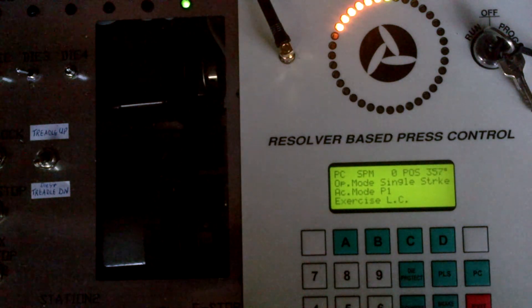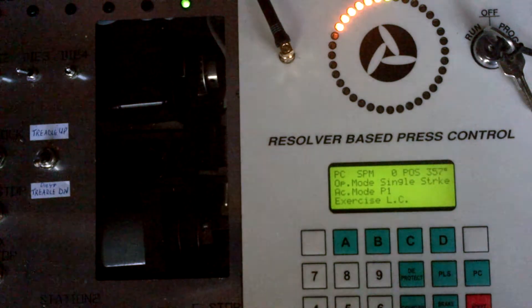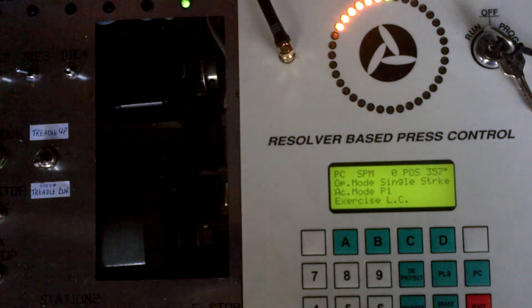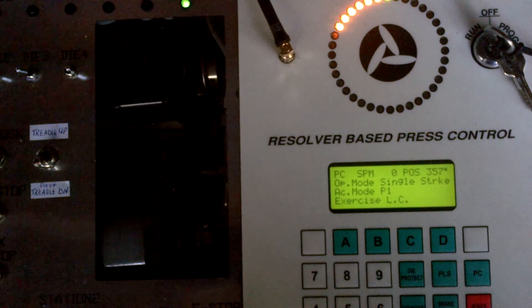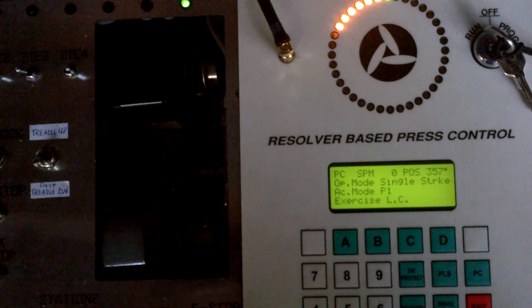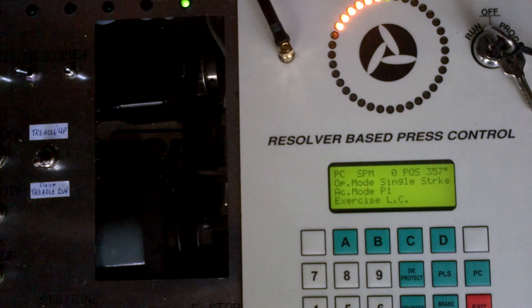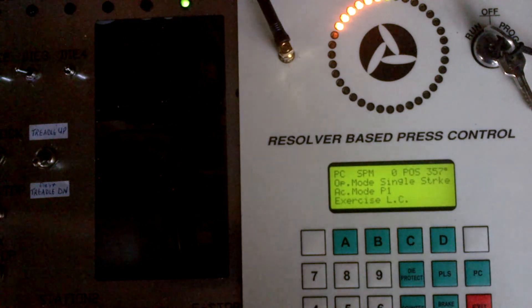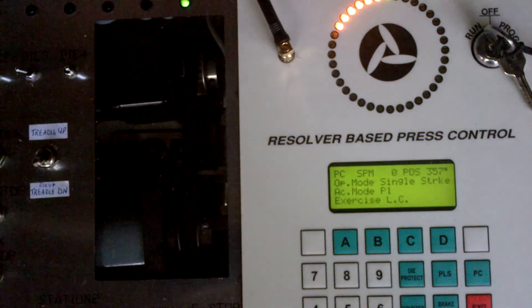So it's a very simple process. It might take several strokes to get it by single stroking and following the prompts to get it to the zero position. But once it's there, from now on, as you're single stroking the press, it's going to continually try to always find zero degrees. It will do that internal compensation so you'll never have to make an adjustment ever again. This is only the first time when you install a new resolver or a new RBPC or mechanically decouple the old resolver that you would have to do the resolver zeroing process.